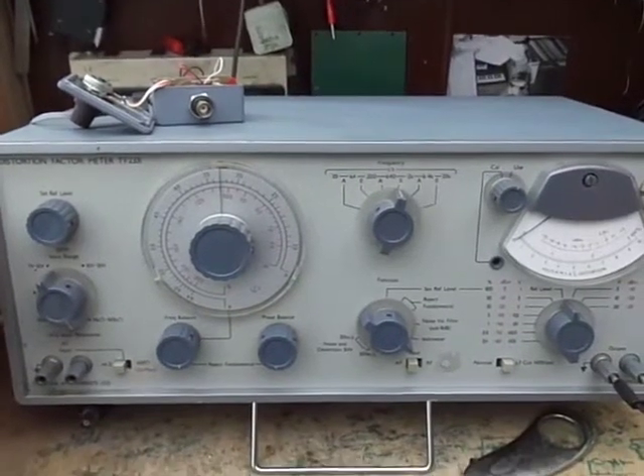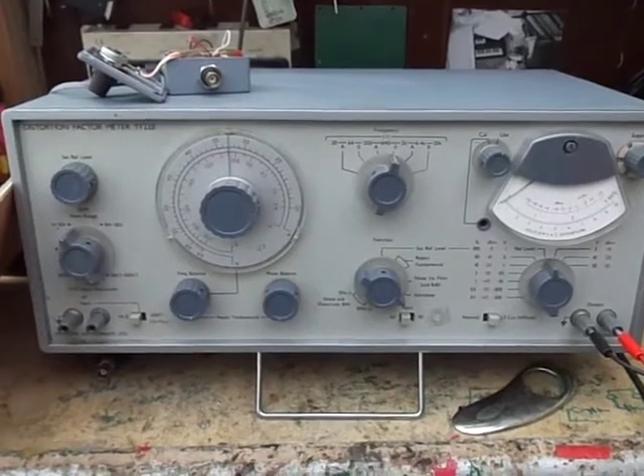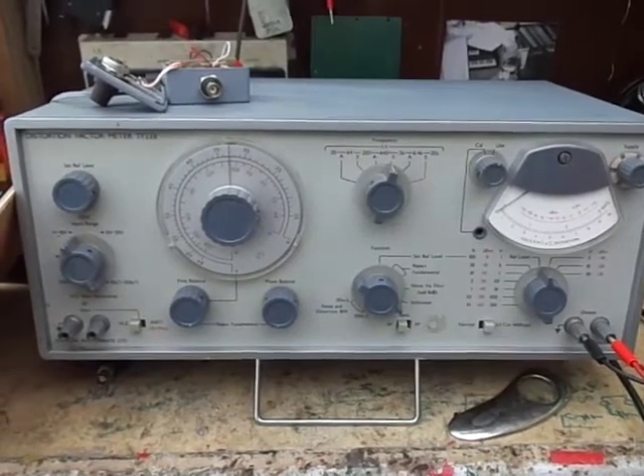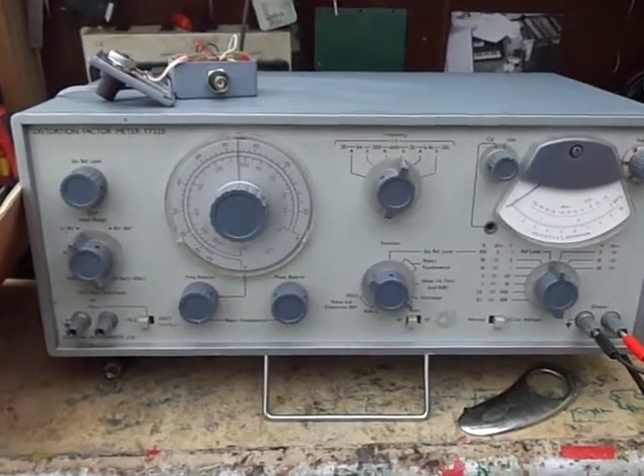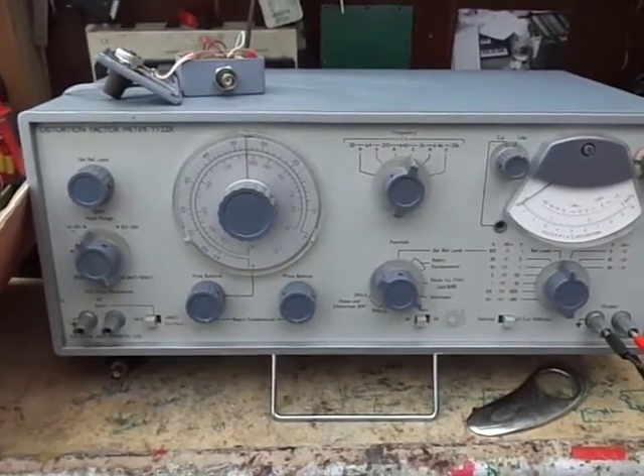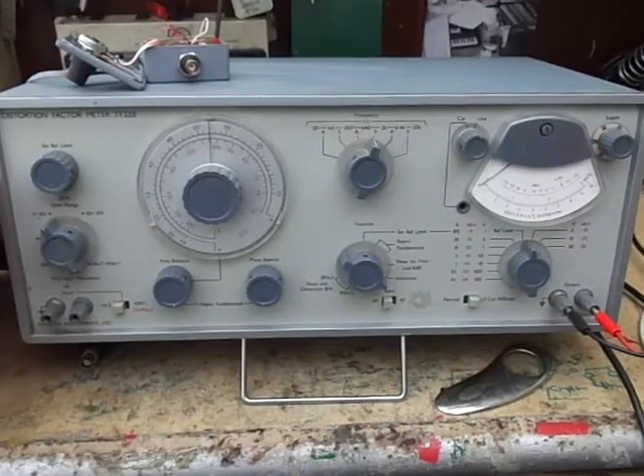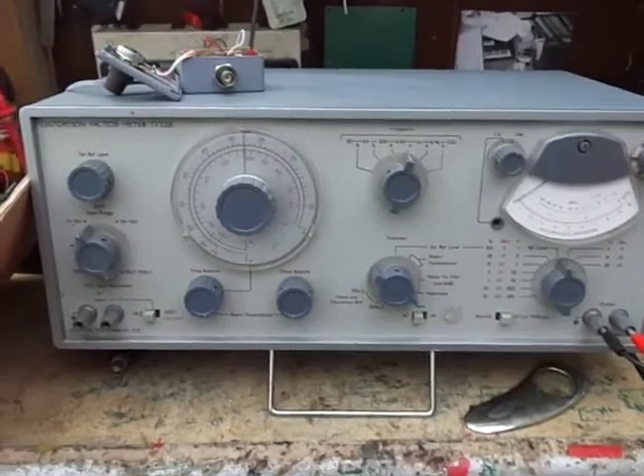Hello there and welcome back. Today on the bench we've got a Marconi TF2331, which is a distortion factor meter or audio analyzer. It measures total harmonic distortion from an input range of 1 to 30 volts and from 20 Hz to 20 kHz. It can measure down to 0.01% THD with reasonable accuracy. So let's give it a go.